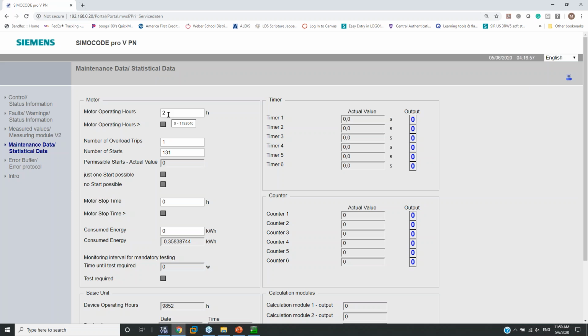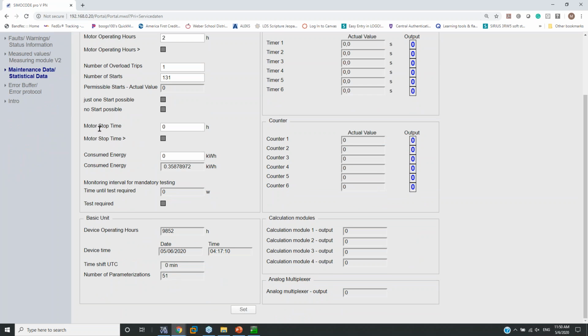My motor has run for 2 hours. That could be that 600-hour set point, that when this motor runs for 600, I send the signal for a new PM. It's done 131 starts in those 2 hours. I've had one overload trip. Stop time, I haven't stopped more than an hour. Energy consumed, kilowatt per hour. My device has been sitting there, meaning the SIMOCODE's been powered up 9,852 hours. Okay, and I've changed its parameters 51 times.